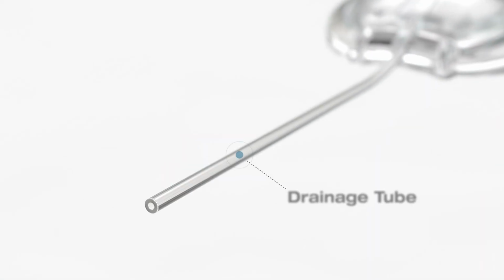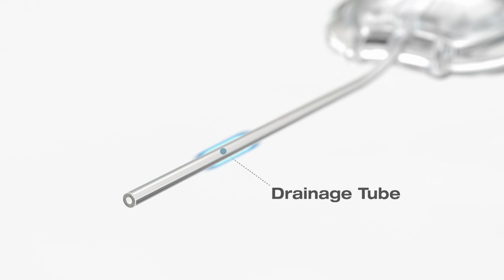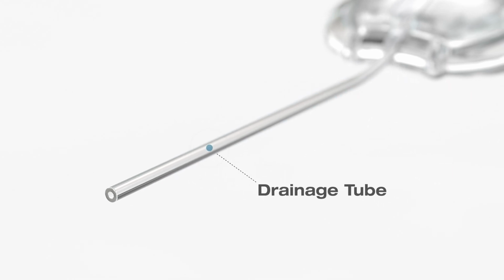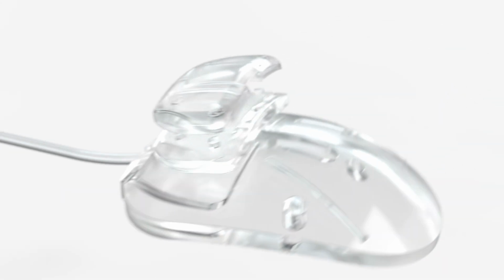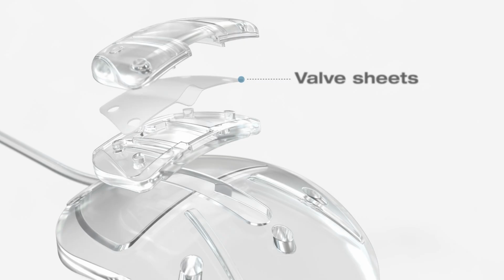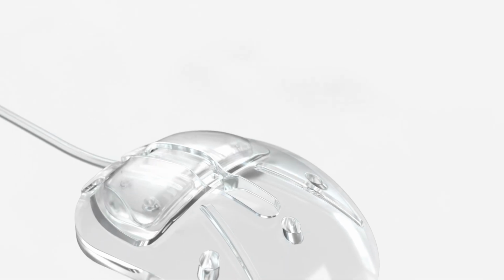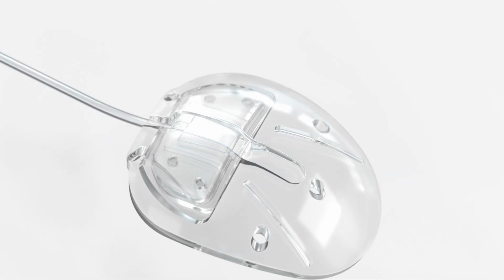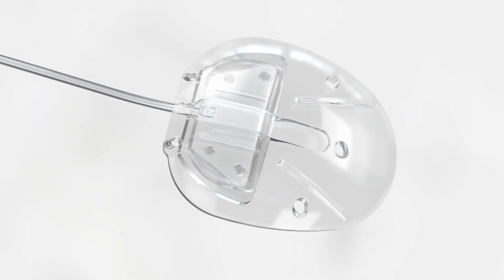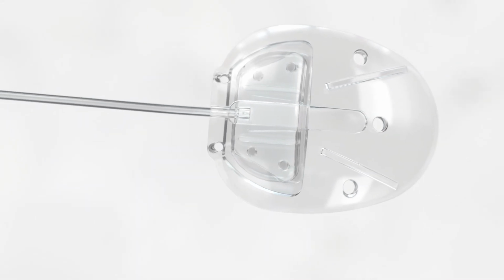The drainage tube allows aqueous humor to flow directly from the anterior chamber to the valve sheets. By changing shape consistently, the valve sheets regulate fluid flow and ensure that the desired pressure is maintained by opening to reduce pressure and closing once pressure is normalized. Each valve assembled undergoes 100% flow and pressure testing to ensure the highest quality and safety standards.